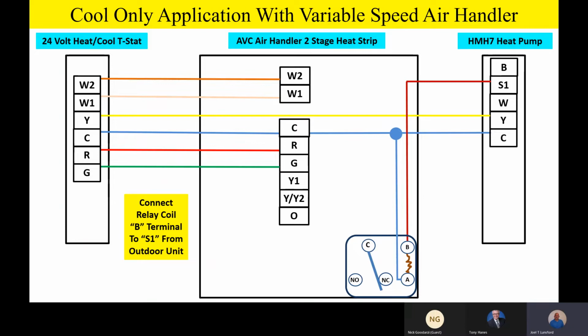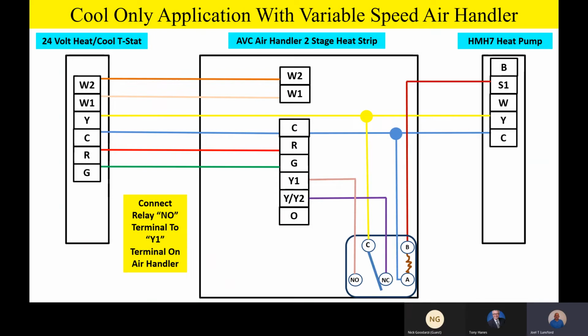Now, if at all possible, especially with the variable speed air handler, you've got this wonderful air handler. If you've got 3 or 4 wires outside, we definitely recommend having this airflow reduction because you're going to have some really wonderful comfort. The common of the relay is going to tie on to the compressor circuit, if you will, or the Y terminal from the thermostat outside, calling for compressor operation. That'll tie onto the common switching terminal of the relay. Normally closed will go up to Y/Y2, and the normally open on the relay will go up to Y1 for our reduced airflow. So anytime we have reduced airflow outside, it's going to drive that variable speed air handler to that low airflow on Y1. So we always recommend the relay if at all possible.